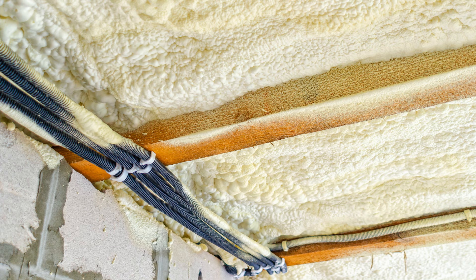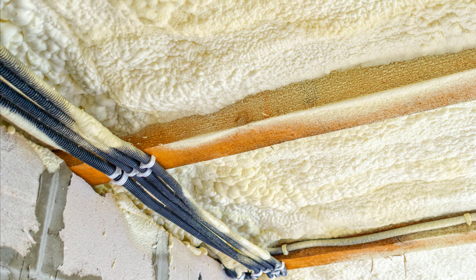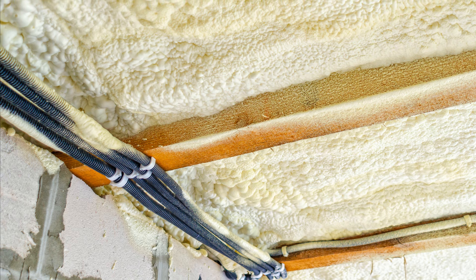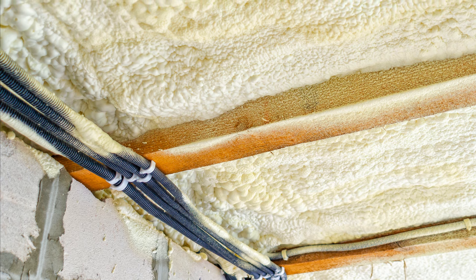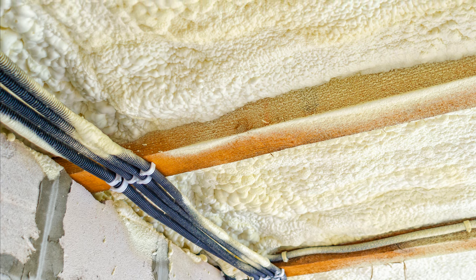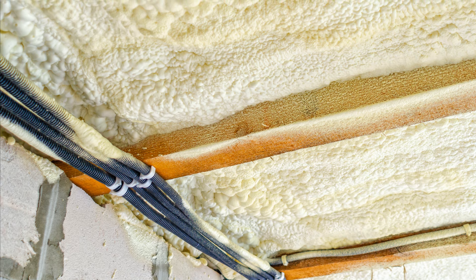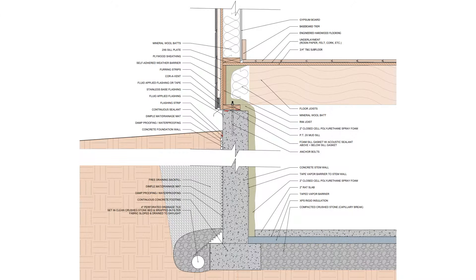If spray foam is to be specified, I recommend that it's allowed to off-gas long before the building occupants move in, and that both air samples and foam core samples are obtained and independently tested for irregularly high quantities of off-gassing chemicals — specifically the blowing agents used. Luckily, the spray foam will be protected from large fluctuations in temperature as it's located below grade or mostly below grade, separated by the thermal mass of the concrete.